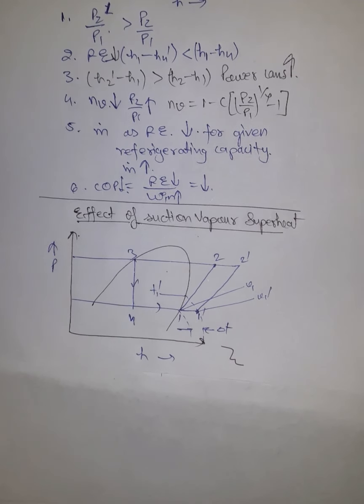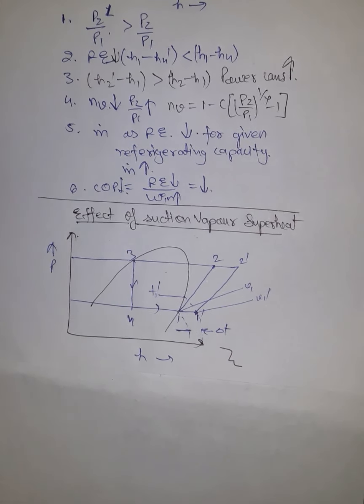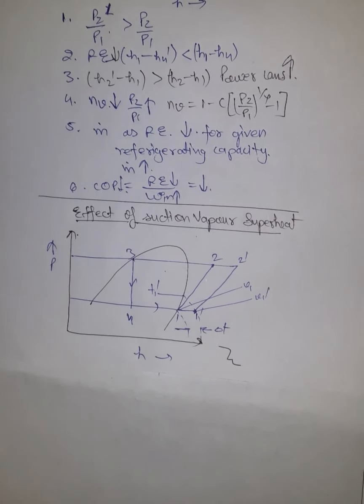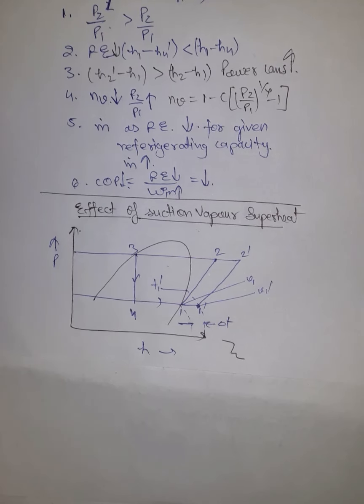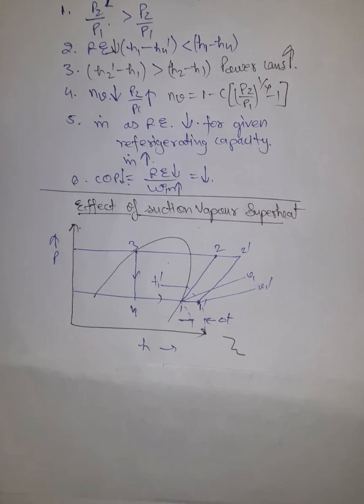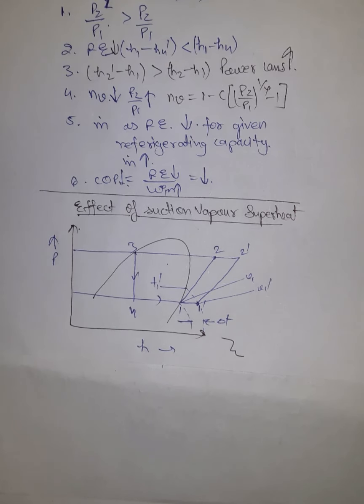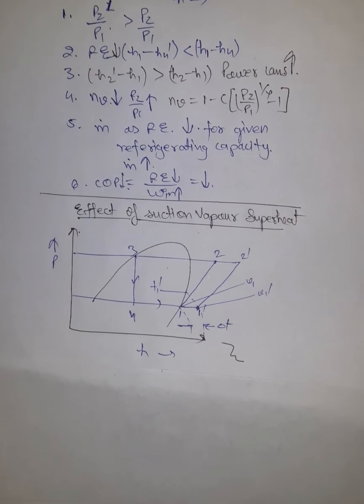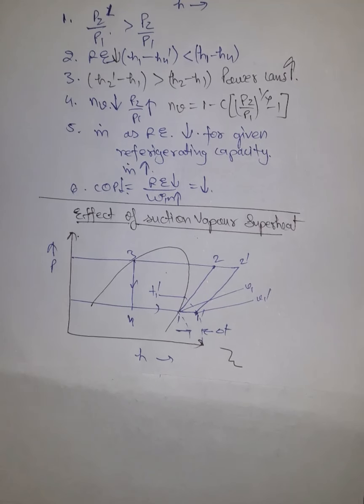Vapor is easily compressed, and compressors are not designed for handling liquid. In most refrigeration and air conditioning systems, the degree of superheat serves as a means of actuating and modulating the capacity of the expansion valve. So that's also favorable, as the design of the expansion valve depends upon this degree of superheat.